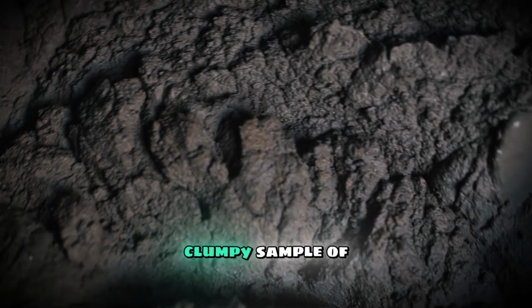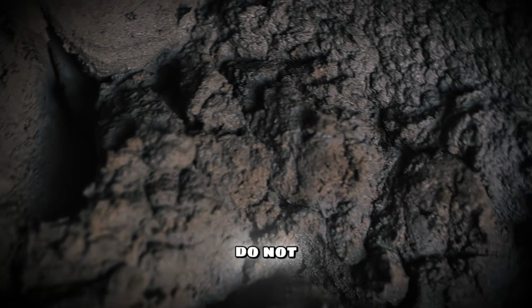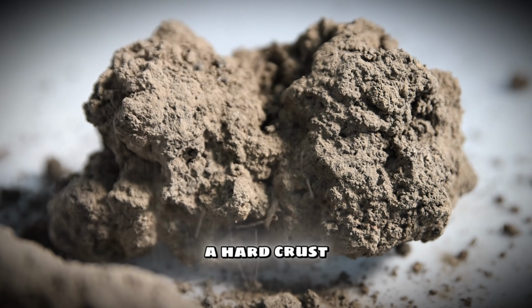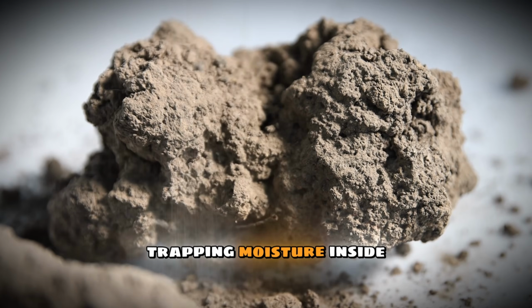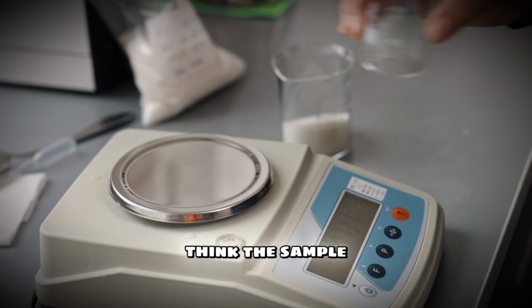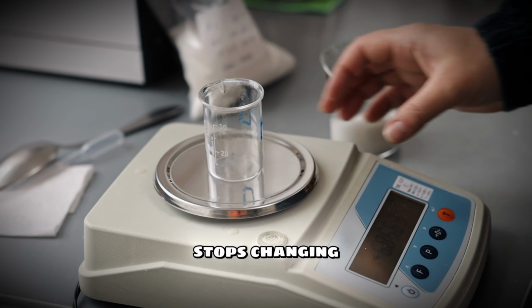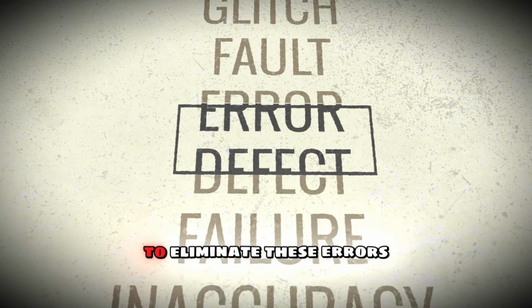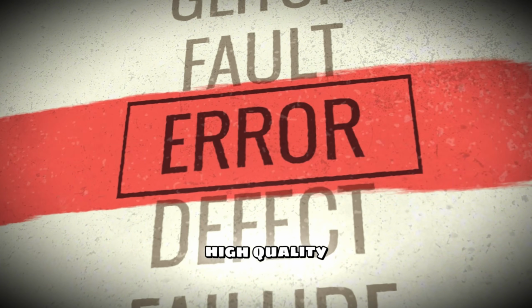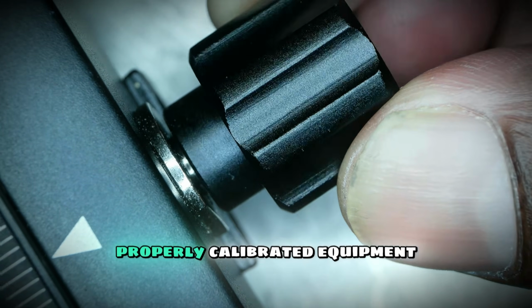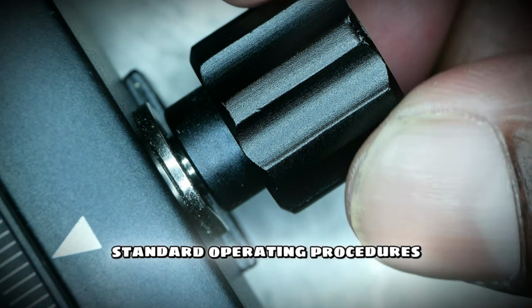If you take a large, clumpy sample of wet clay and do not spread it evenly across the sample pan, the surface will dry and create a hard crust, trapping moisture inside the clump. The machine will think the sample is fully dried because the weight stops changing, but hidden moisture remains trapped inside. To eliminate these errors, you must use high-quality, properly calibrated equipment and follow exact standard operating procedures.